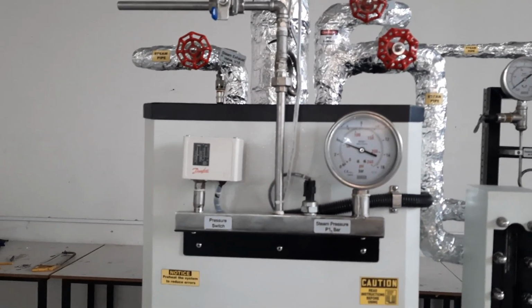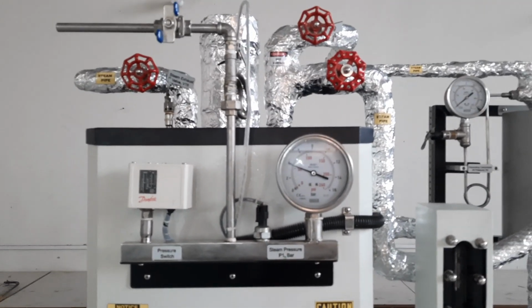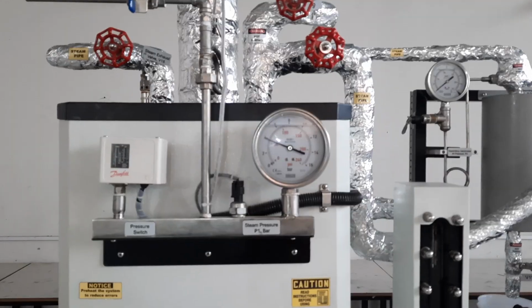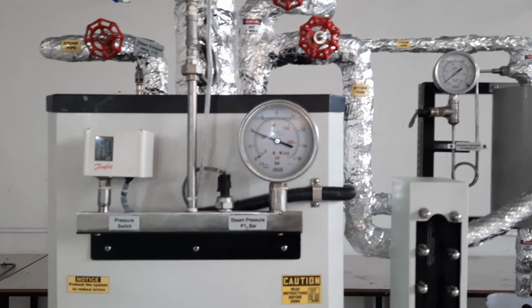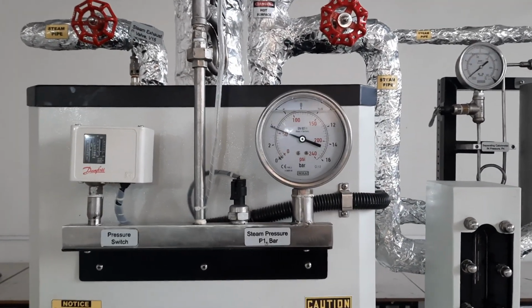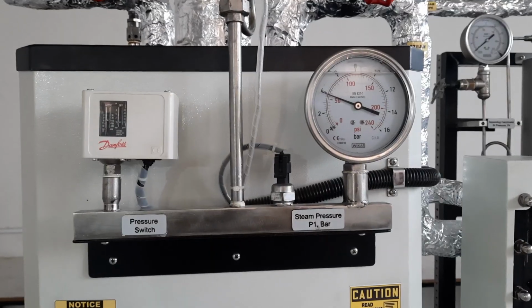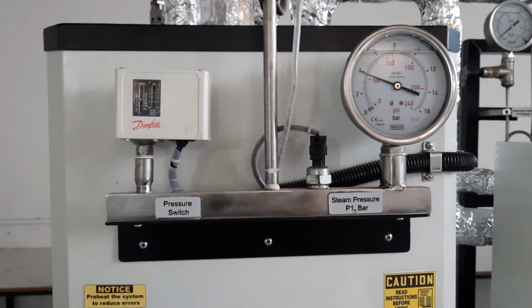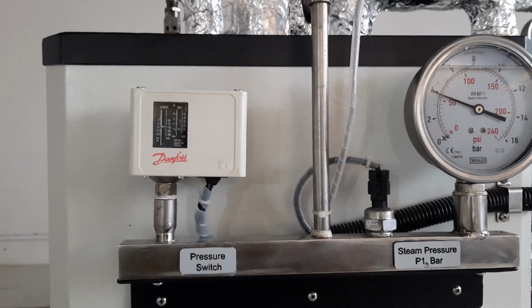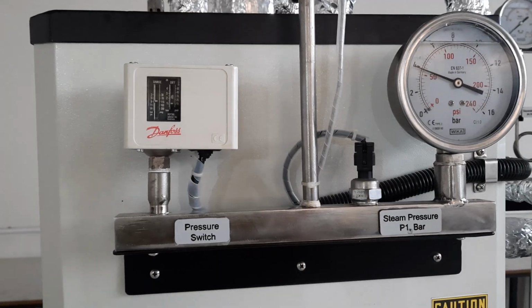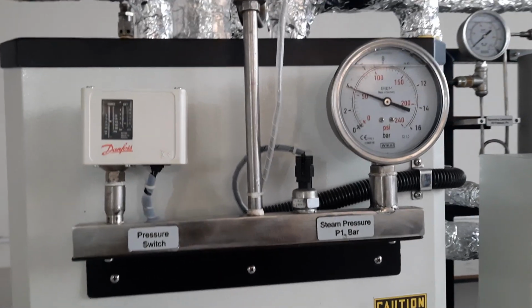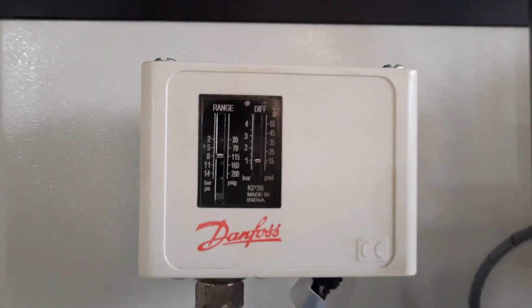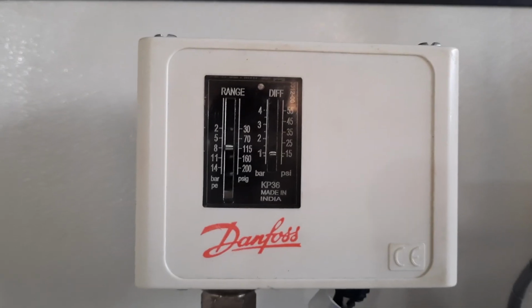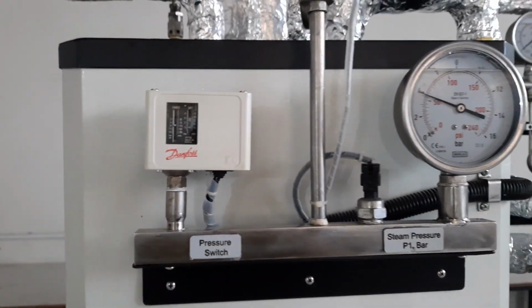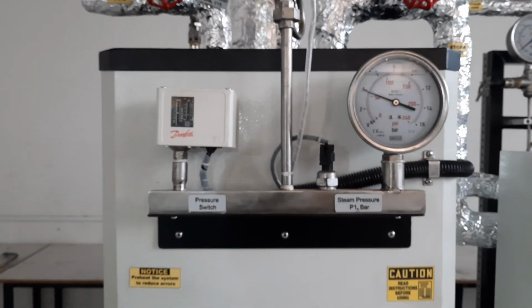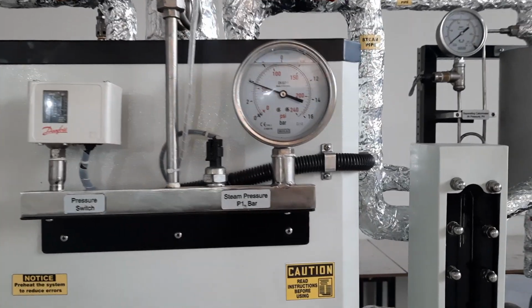The boiler has a pressure gauge and a pressure sensor attached. This is the pressure switch, which trips the burner at the set pressure. Right now it is set at 8 bar. The burner will shut down when the pressure reaches 8 bar.